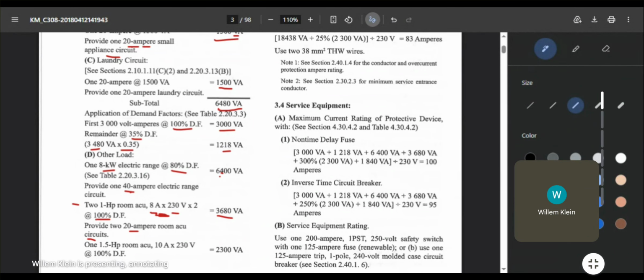Okay, and then after that, you have one 1.5 HP aircon. This is the bigger one, for let's say the master's bedroom, or your living room. And so 10 amperes at 230 volts. That's 10 times 230, so you have 2,300 VA, at 100% demand factor. Okay.